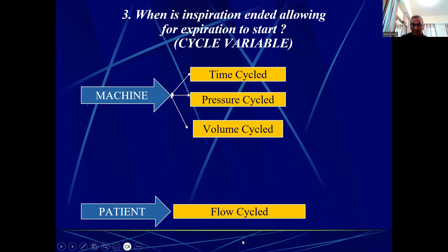Now there is a peak flow. Inspiration, you follow my cursor, right? So the flow is reached, the peak flow is reached. And you have reached certain pressure limit you have set or volume limit you have given. For example, you have given 200 cc of tidal volume or a peak pressure of 20, that is reached. Once that is reached, what happens? Slowly the flow decreases, right?